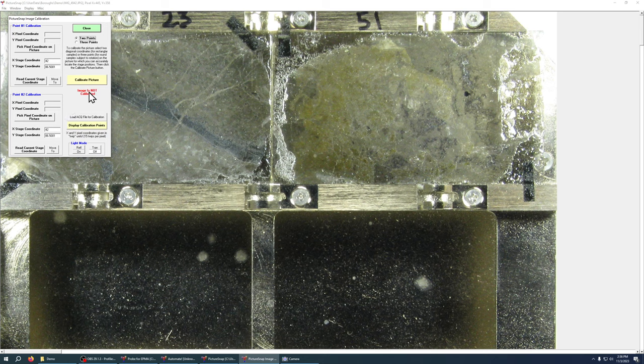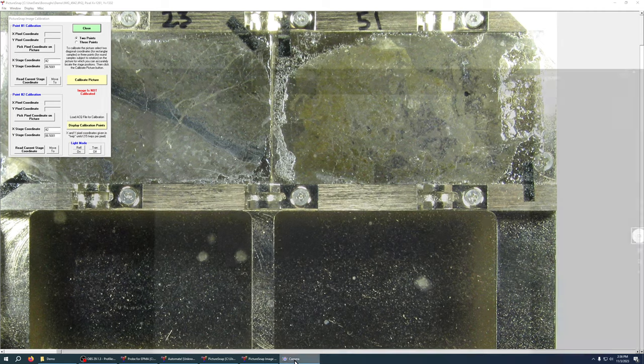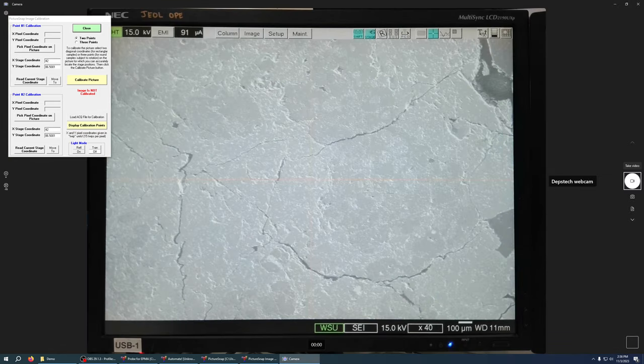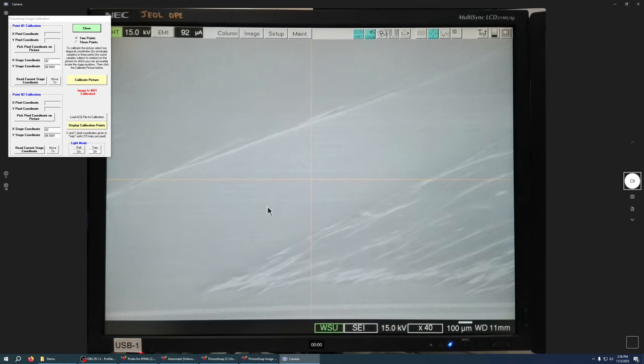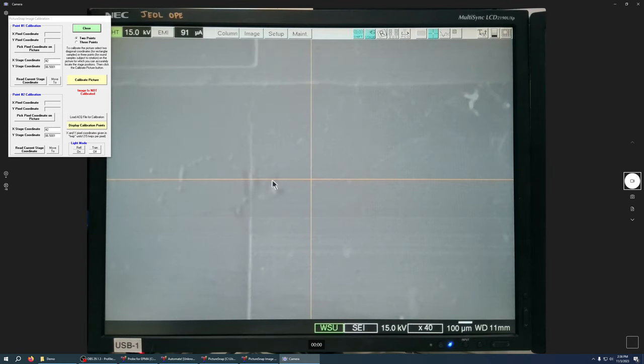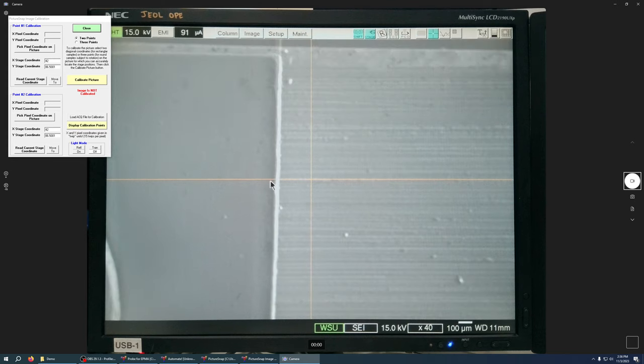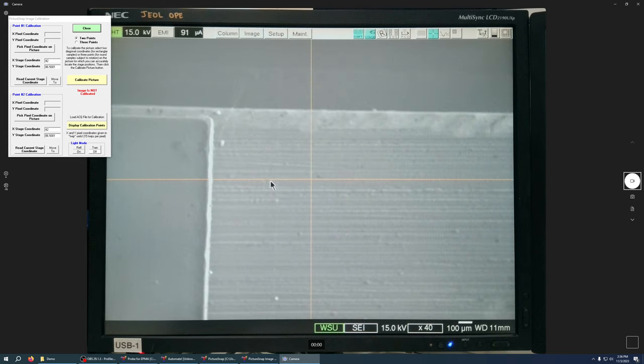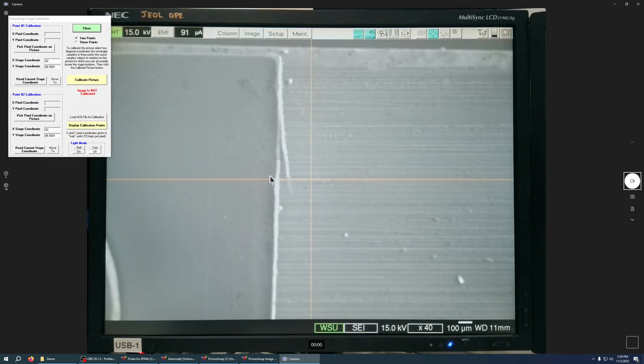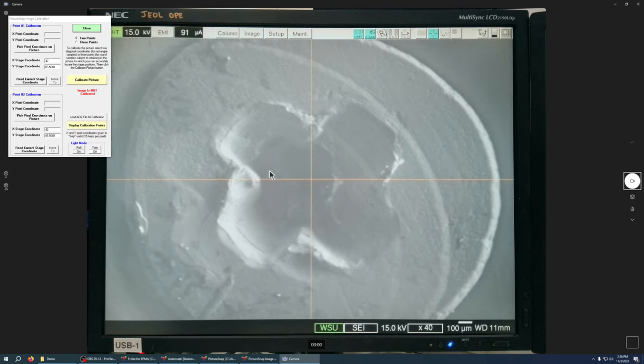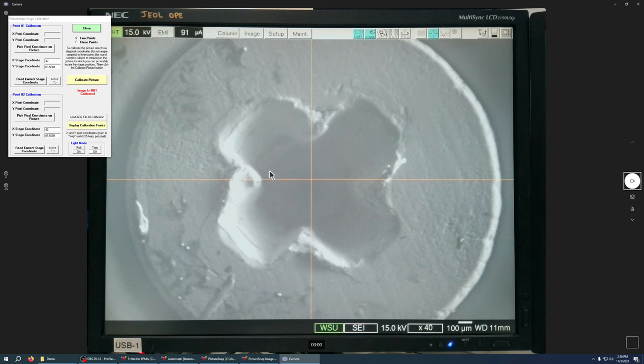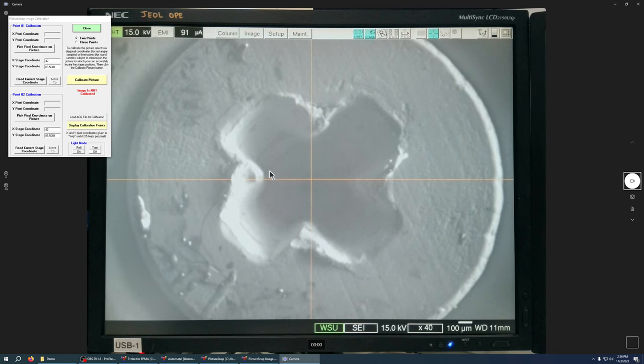So what I need to do is I need to find a couple of objects that I can see with the scope and see on the image and I like to choose these screws that are on my sample holder. So we're going to go ahead and navigate to one of those screws and we want to line it up with the crosshairs as best we can in order to get the most precise calibration. So there's my screw, I'm going to dial it in here, get pretty close to the center.